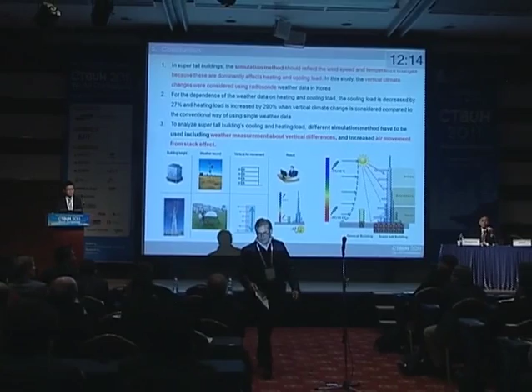Well, any questions from the audience? Well, let me ask one question. When you calculate the cooling and heating load, you use the air change method for calculation of the heating and cooling load. So I just ask, you measured the wind velocity at each level of the height. So why didn't you use your wind velocity data for calculation of the infiltration load? Because if you have a wind velocity, you can use your wind pressure coefficient, and then you can use a leakage area method for infiltration load for heating and cooling.